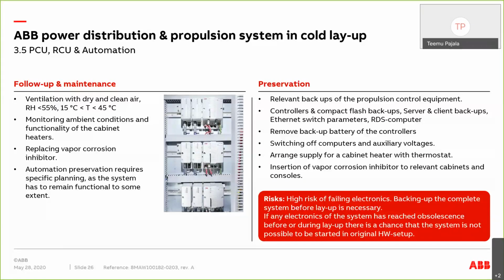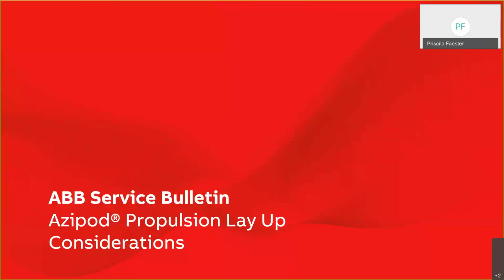And that relates to all the controllers, servers, clients, Ethernet switches, RDS computer, all the equipment where we have software and parameters in use. And after that, backup batteries can be removed from the controllers, especially if it's a long period of time planned on layup. Batteries lose their energy anyway, so it's better to remove them so that they don't start to leak or anything. And then after that, all computers can be switched off. Auxiliary voltages can be switched off. That was the electrical side and automation side. And next we move to the Azipod related considerations.